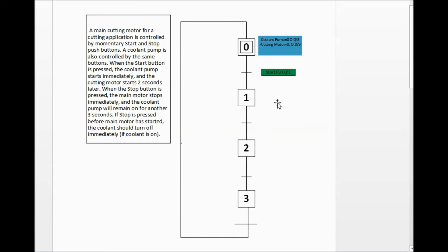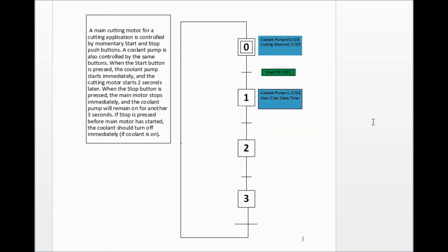Once the start button is true, we can define the outputs at step 1. At step 1, the coolant pump is set to 1 — high, turning it on — located at O:0/8. We also start a two-second delay timer at this step. The next transition requires us to wait for that timer to complete before we can start the cutting motor. So the transition is the two-second delay timer done bit becoming true.